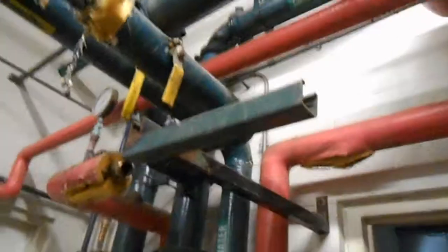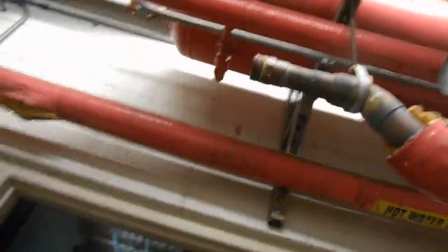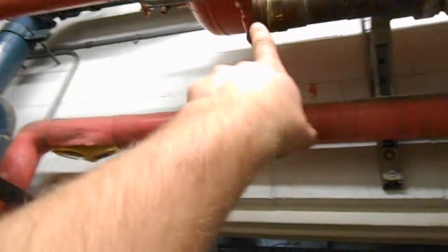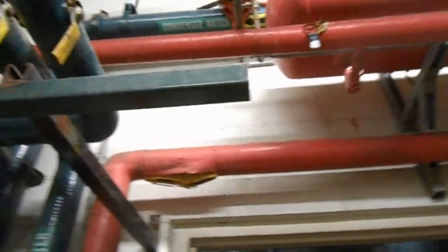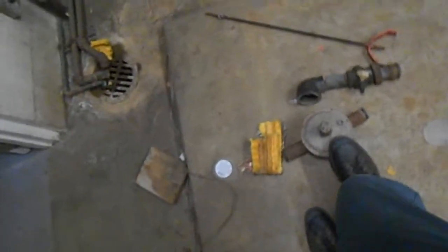We also got our hot water recirculating pump — I didn't show you that before. But the idiots who put it in replaced it. The guys who did the job originally were well-qualified pipe fitters. Anyone who came in to do repairs was a bunch of cheap low-bid hacks. They had this from copper to galvanized and black iron — the galvanized coupler right here, black iron is all rusty. Iron unions and same thing over here. Anyway, the pump was toast, so we had to take it down. We got that down, got the other heat exchanger down, got these tanks out of here. Gas main was coming down right into the old boiler, so we unthreaded that piece. We saved our little gas valve and regulator — we can probably use that.